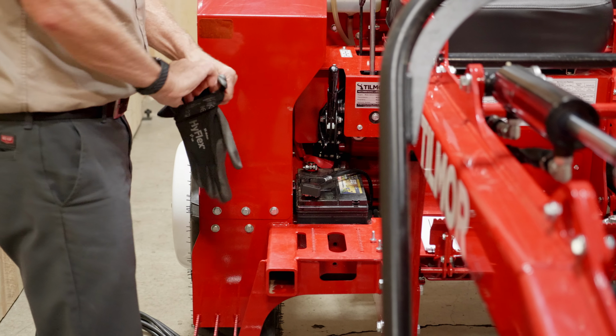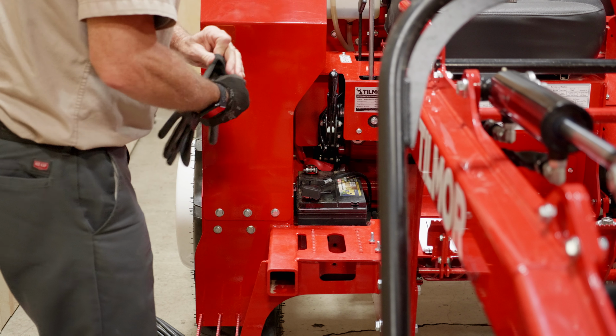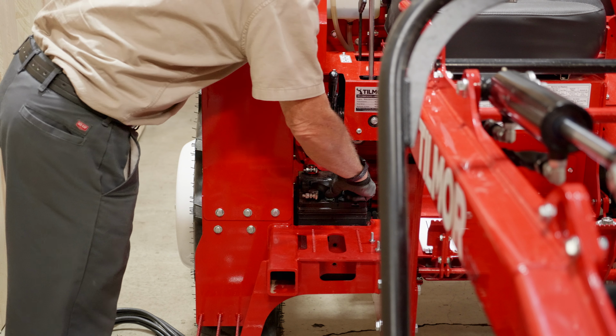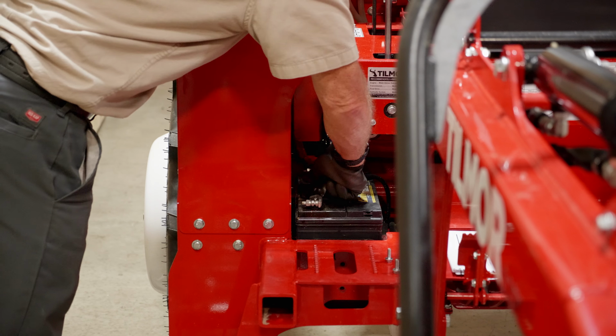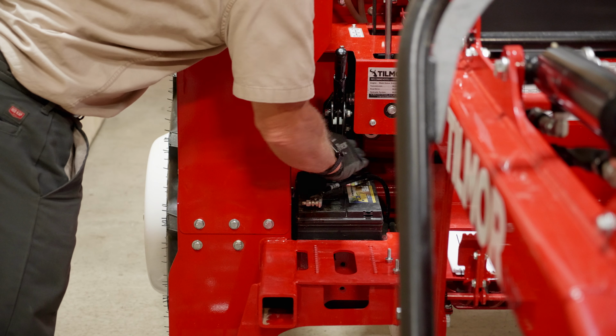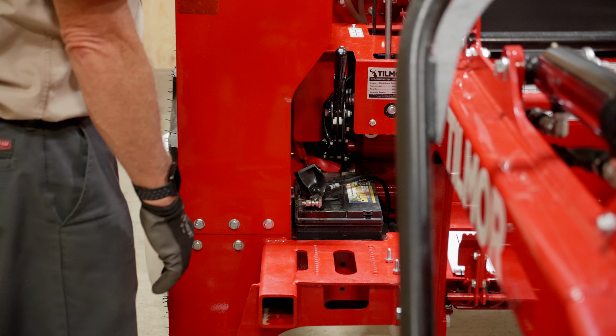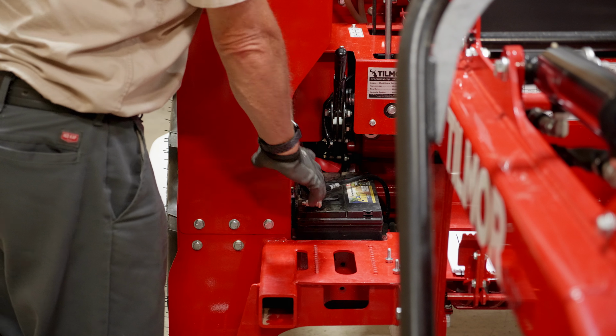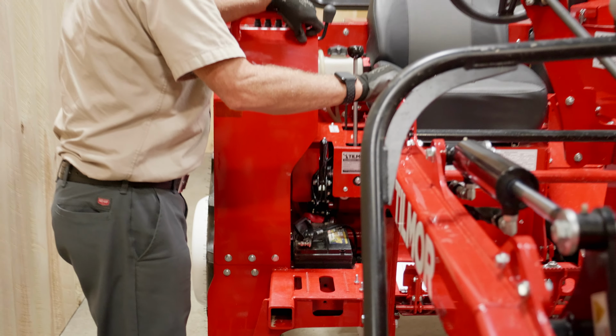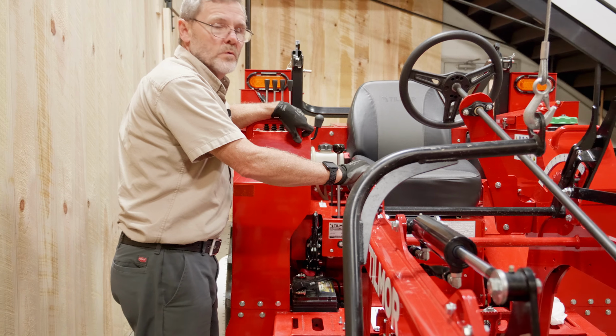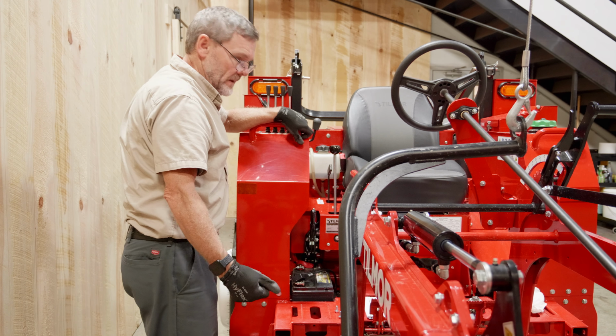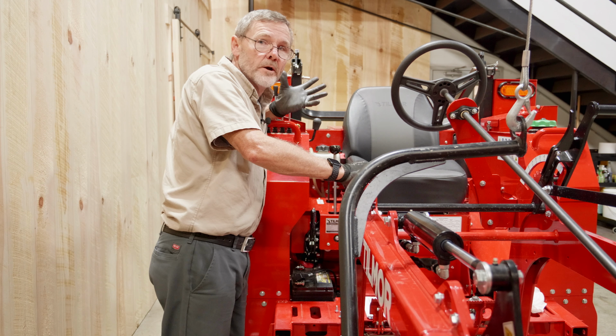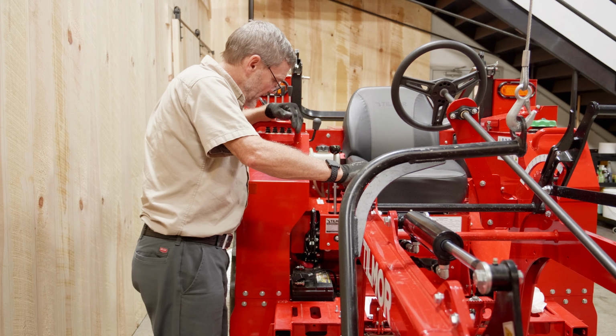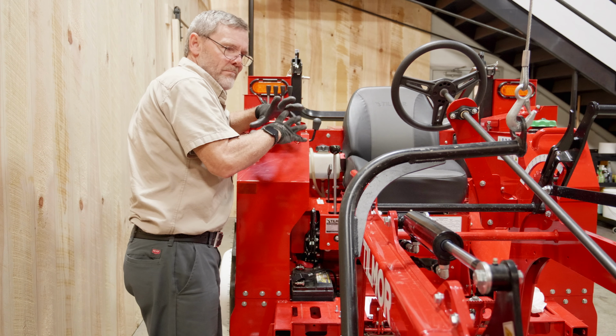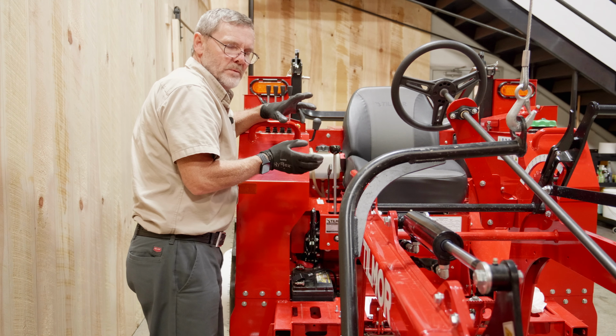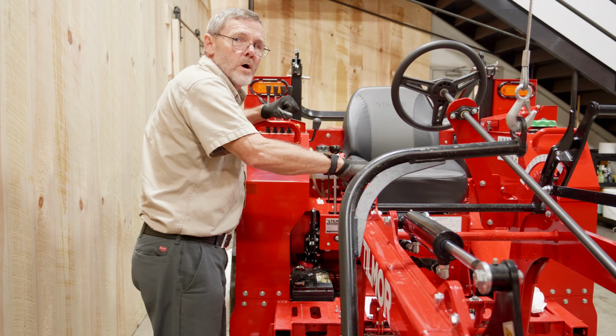We'll put on our PPE. Occasionally, for maintenance, if you inspect the battery with some frequency, we want to make sure it's clean. Occasionally there might be some corrosion. If it's just corrosion on the outside, it can be cleaned with a solution of maybe 4 tablespoons of baking soda in a gallon of water, which will really do the trick. After you pour that on, you'll see the bubbling and the corrosion disappears. Make sure you flush the area with clean water.